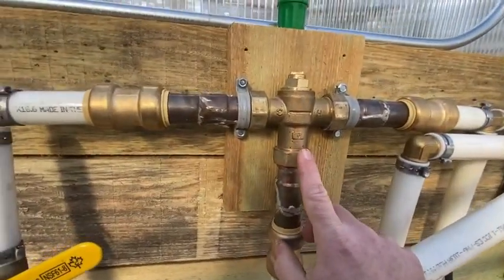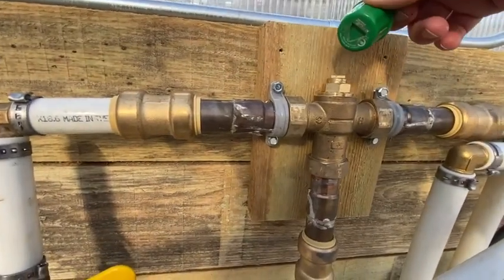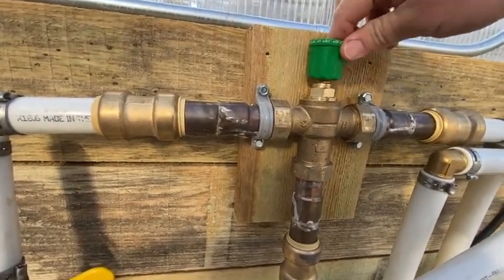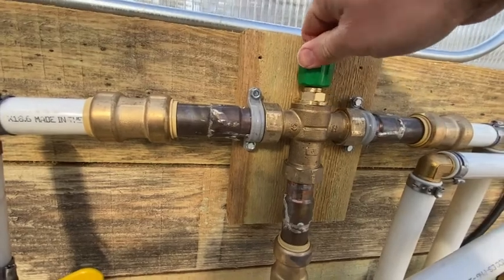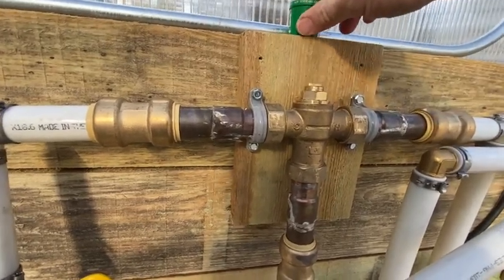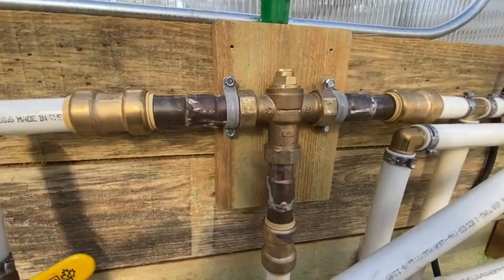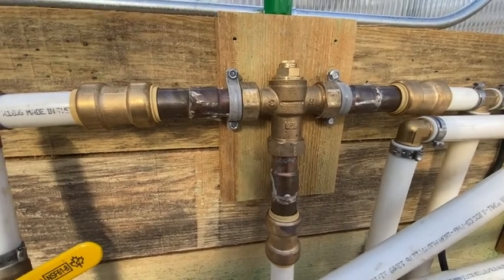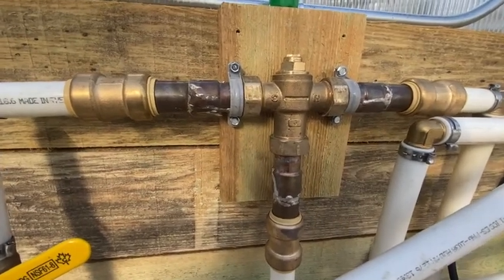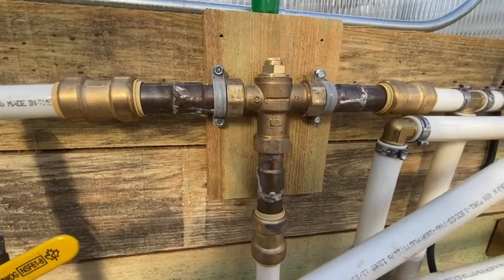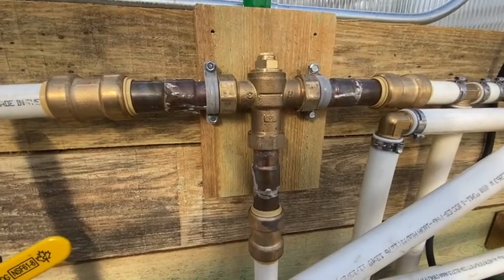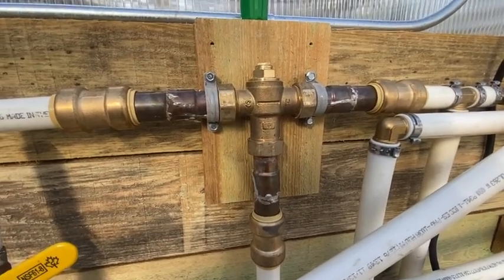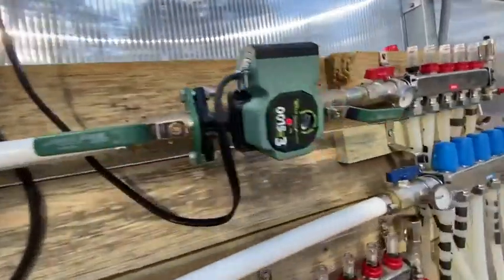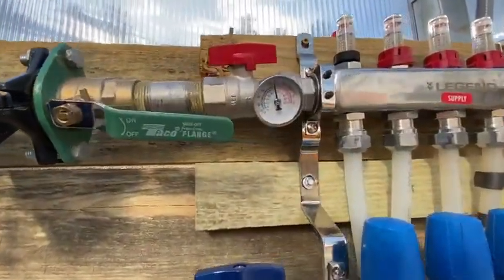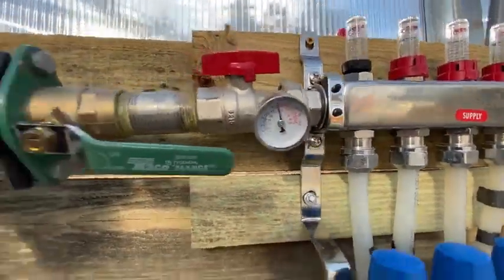And here's where you just take the cap, turn it upside down, click it down on that little triangle, and you can turn it right or left to adjust the amount of cold going back so you don't get too hot of water. Our tank can produce—well, we've got it set at 160, but we don't want 160. We want about 120, which is what we got there going in.